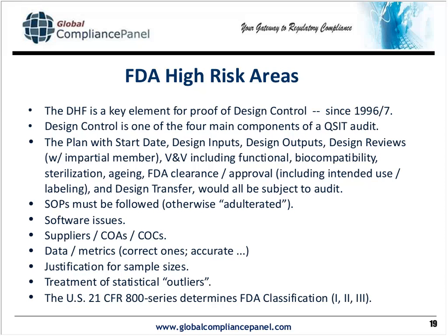And one of the key, or 2 of the key areas they're really interested in are certificates of analysis and certificates of compliance. So if you as an R&D developer of your product are going to be outsourcing key components, you need to recognize that you may be accepting those in, and your QA people will be taking that and developing the documentation to do this based on acceptable COAs, certificates of analysis, and certificates of compliance. The FDA knows this, so they want to know what's behind the numbers on those COAs, COCs.